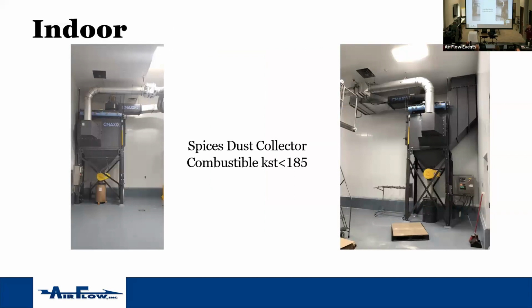Indoor units, we've shown a lot of outdoor units in these slides. Here is an indoor unit, really hard to see, but this is an outside wall. And it's on spice system, it has a KST, so it's explosive. This is an outside wall right here, and this is where the explosion device is located, the explosion panel on the collector. You have a set distance that you can duct that to the outside. FIKE will rate that, whoever manufactures that explosion panel, they'll rate that distance and tell you based off of that KST, based off of this panel, you have a set distance that you can run to get to atmosphere outside. This one in particular goes right outside.